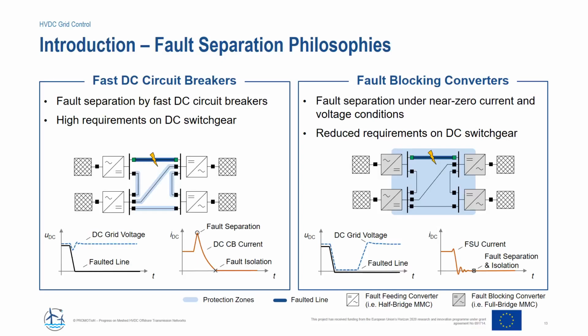For sure, after the fault separation, also the DC grid voltage has to be restored, and overall there's a high amount of coordination between the converters, the switchgear, and the overall grid control involved here. And due to this high complexity of the protection strategy, it is important to demonstrate that the DC fault controls of the fault blocking converters properly work in post-simulation, but also in the physical DC grid which we have built here, that the fault separation process itself and the communication or coordination between the MMC converters and the fault separation unit works properly, and that the DC grid voltage restoration commences after the overall fault separation process.